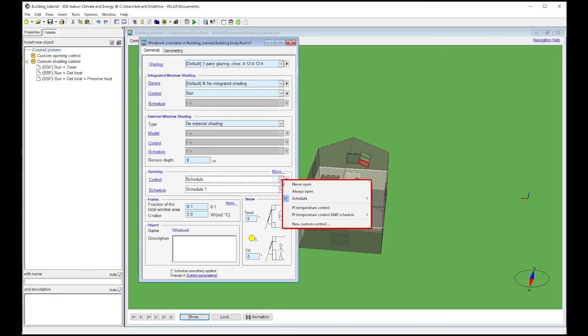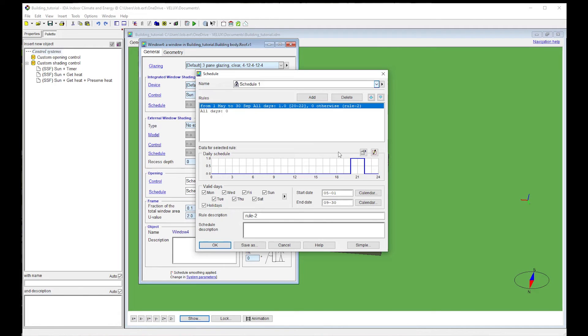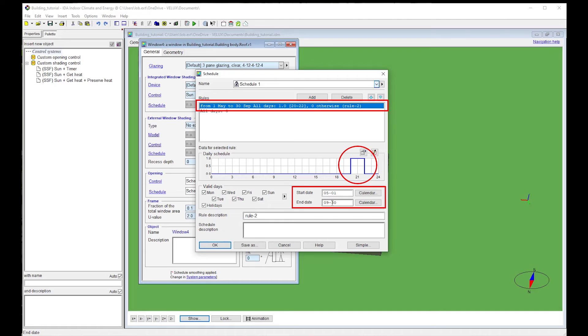PI temperature control means the windows will open according to a temperature threshold. PI temperature control and schedule means the windows open based on temperature but also according to an active schedule. We will set a schedule opening control to model a ventilative cooling strategy, where occupants open the windows during summer evenings to cool the building. We set the windows to be open from 8 to 10 pm from the beginning of May till the end of September.